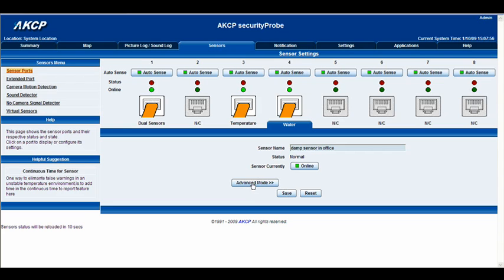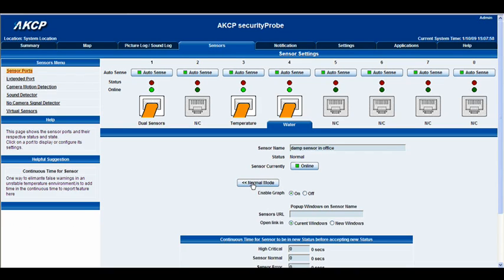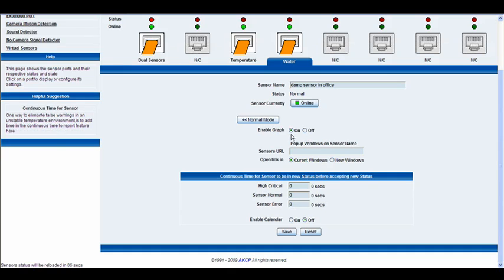So let's have a look at the advanced mode. Here we are in advanced mode. You can see we can toggle the graph on or off. We have the sensor's URL where we can type in a website and open it in the current window or a new window. Below that we also have the continuous time — the duration the sensor must be in a new status before accepting it. For example, entering 10 seconds means it would have to be in a high critical status for 10 seconds before it actually gives you a readout of that high critical.